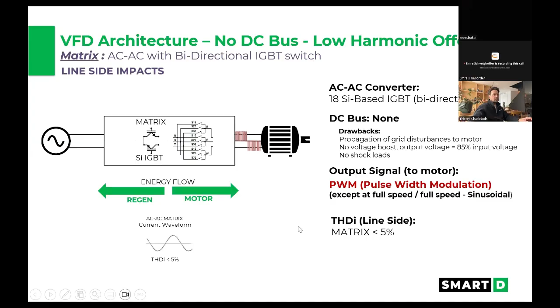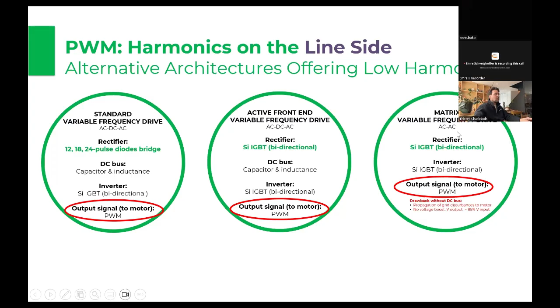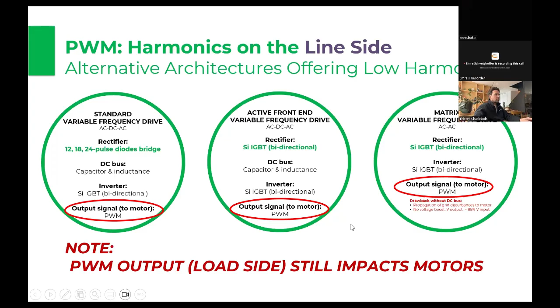So just a quick review on that first part here, on the line side problem, line side harmonics. A standard VFD still has this output signal that's a square wave. Even an active front end, all the active front ends out there, typically up until this point in history, still have a pulse width modulated square wave. And then, of course, any of the experimenting of the active front ends that's been happening, they still have this drawback, not only in the design, but still with a square wave to the motor. So we still have an impact going there.